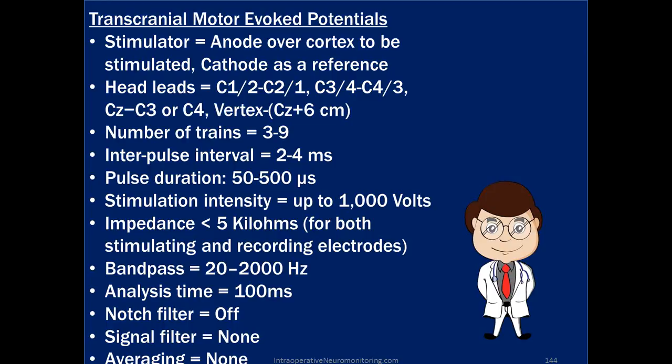Impedance less than five kilo ohms for both stimulating and recording electrodes. Band pass is pretty wide open at 20 to 2,000 hertz, because remember these are very large amplitudes. We don't have to worry too much about noise, so we only have to trigger one response to collect the CMAP, so there's no averaging. Analysis time is a hundred milliseconds total.